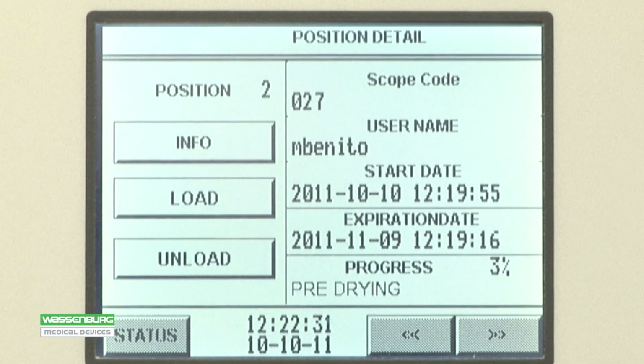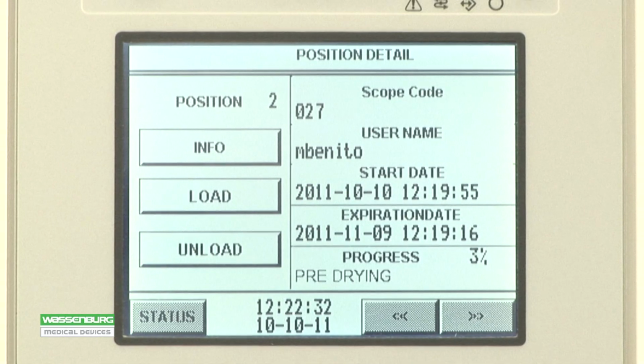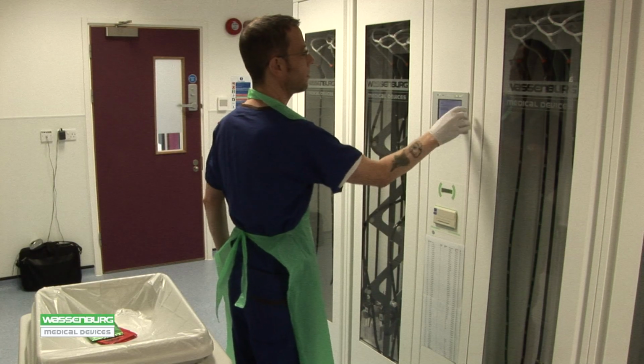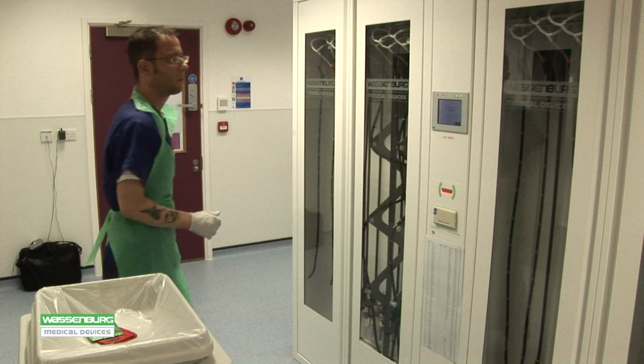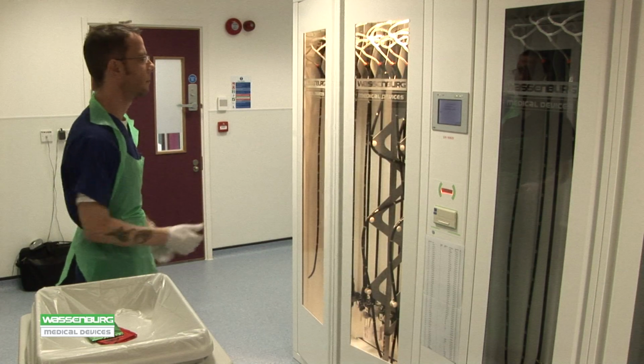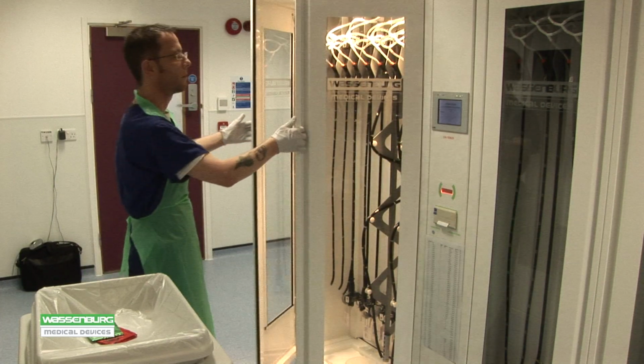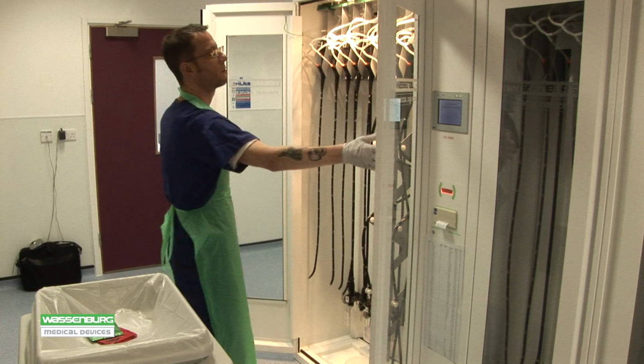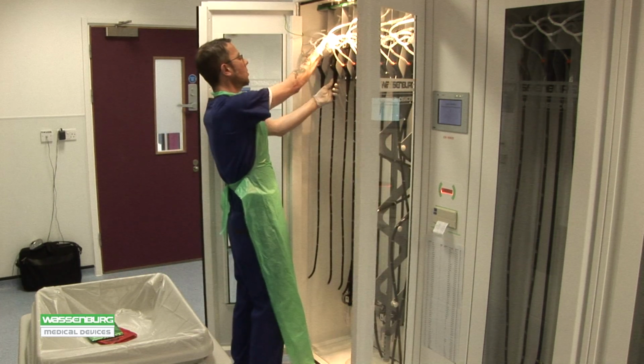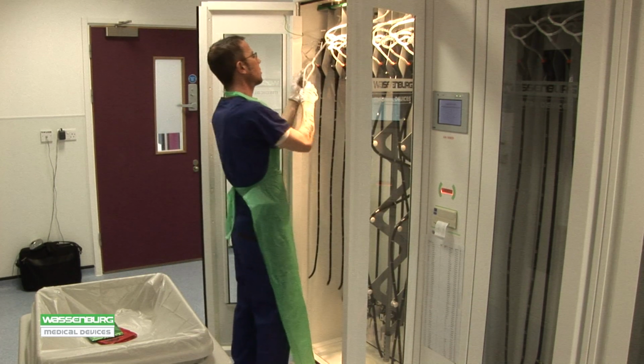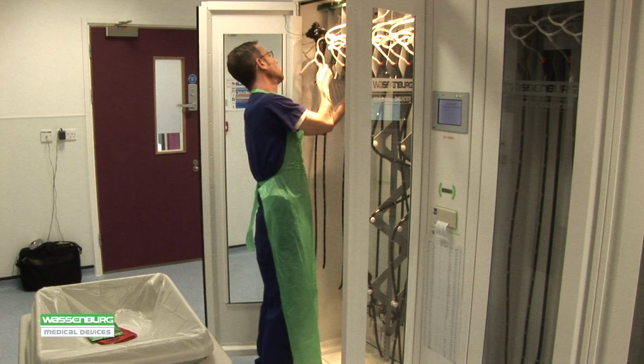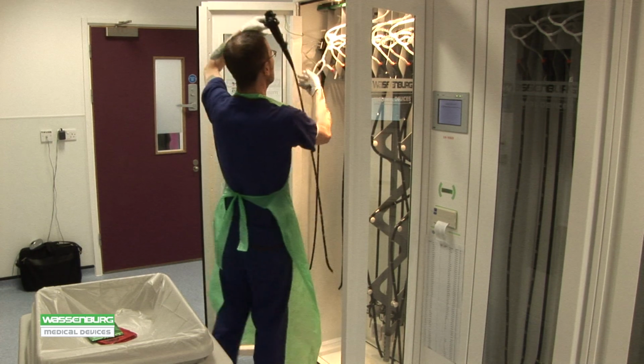40 scope storage places are provided in the Dry 300 cabinets. Scopes for the morning list are removed from the cabinet in sequence or expiry date order. Each cabinet is provided with a range of hanging brackets to suit the scopes being stored and specific connector blocks and channel connectors for each scope. Scopes can be stored for up to 30 days whilst maintaining post-wash and disinfect condition.